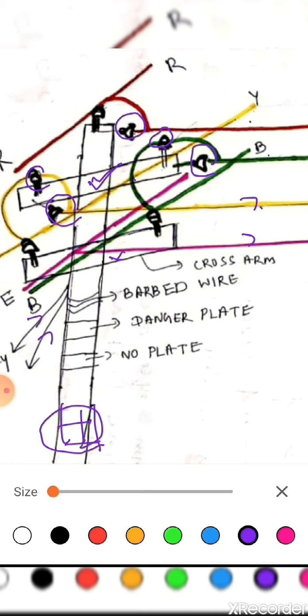Next, an earth wire clamp is required. Here the earth wire is going in this direction and we have to take the earth wire along this direction. So one earth wire clamp is needed to connect the earth wire with this pole. Next is the T clamp for the MS channel. This is the MS channel, and the MS channel will be fixed to this pole through a T clamp. So the quantity of T clamp is 1.